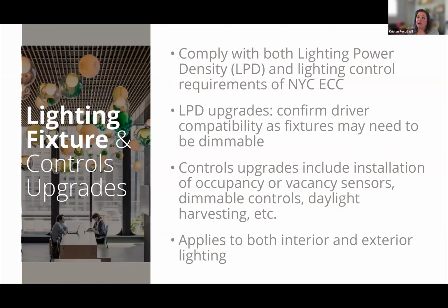So what is actually required under this local law and the energy code? There are two parts of the lighting side. One is the lighting power density allowances, which are calculated in watts, that are prescribed under the energy code. This is basically watts per square foot allowed based on either the building area method or the space by space method. The building area method prescribes a certain lighting power density, watts per square foot, based on the building's overall use type. So an office use type would have a lighting power density allowance of 0.79 watts per square foot, while something like a museum would have a higher lighting power density of 1.06 watts per square foot. Depending on the type of building, that would dictate what the overall allowance is, and then you'd do a simple calculation based on the square footage of your building for the overall allowance.